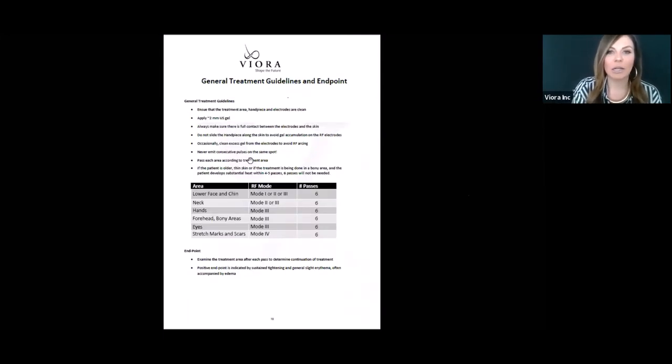Okay, so I'm going to stop here and just point out a few things. We're always using ultrasound gel with this handpiece. So glycerin, 100% vegetable glycerin with the V-form, and then always ultrasound gel with the VST. Always make sure that you are ordering clear ultrasound gel. Do not use blue or green. Blue or green can be cheaper. However, there's dye in it, and the dye cannot withstand very much heat. So what happens is it melts down, it becomes thin, it slides off the face, and really the biggest thing is using thick ultrasound gel with this handpiece.